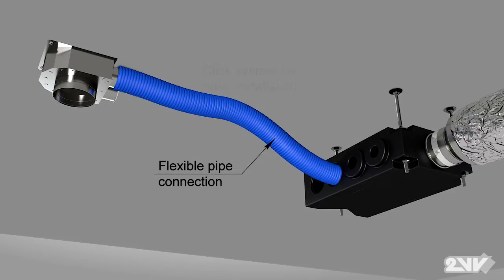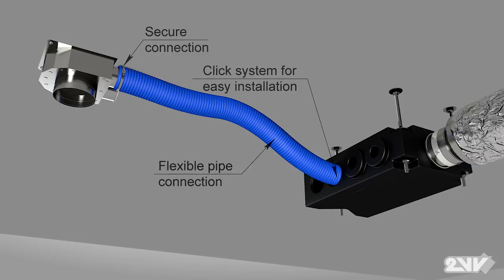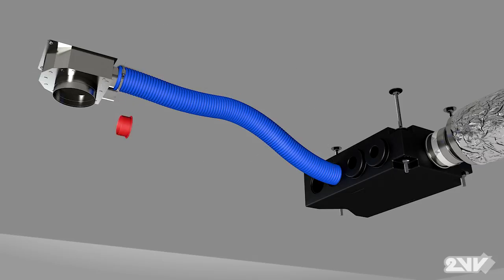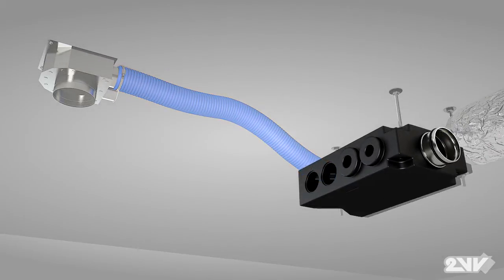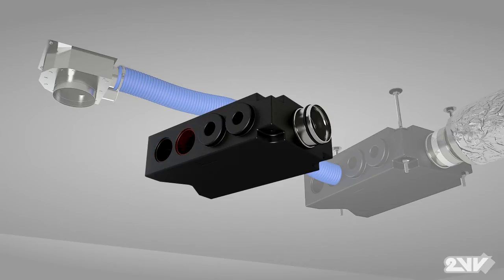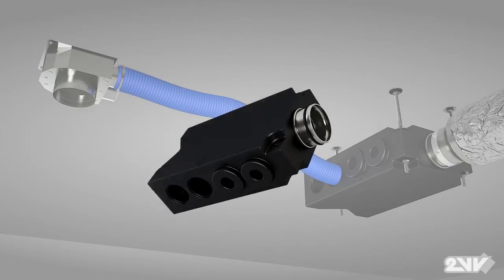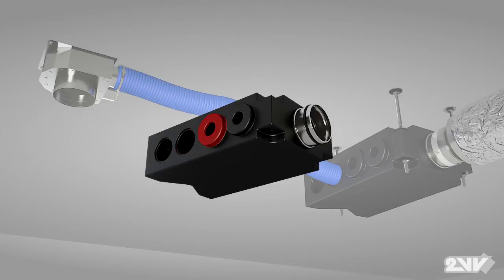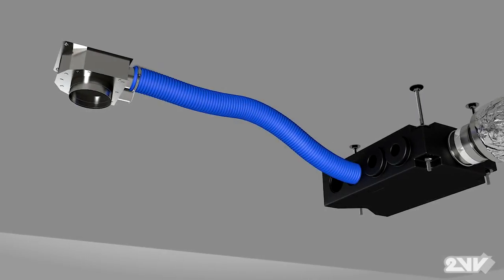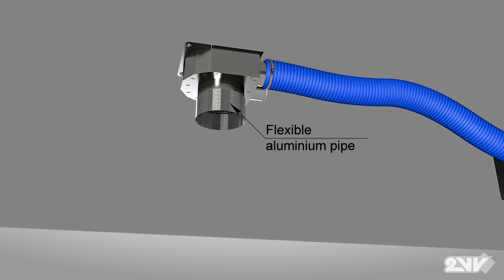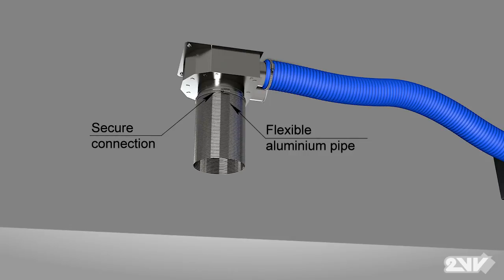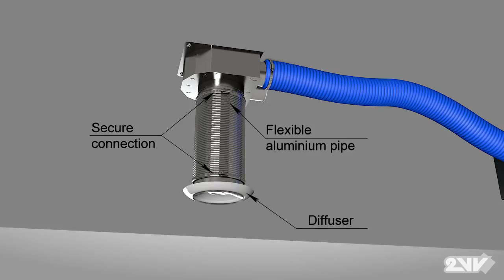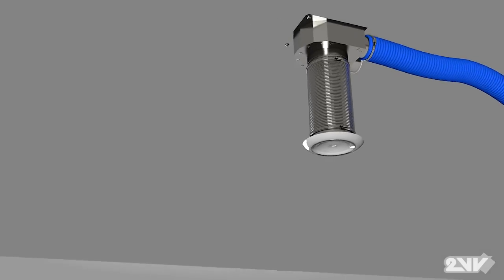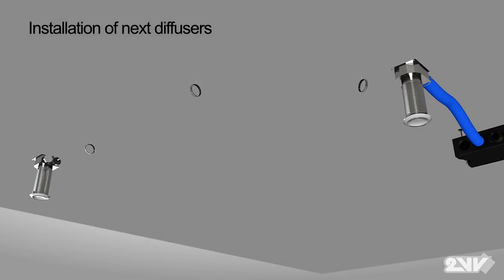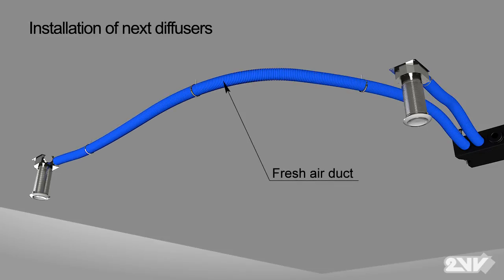Now connect the duct outlet using ductwork flex hose to the distribution box. Using clamps, secure the ducts to the distribution box and the diffuser. Taking the flex duct, attach it to the diffuser and the grill and fasten using clamps. In the same way, install additional diffusers and grills to the supply branch of the distribution box using loop hangers spaced at 2-meter intervals and attached to the ceiling.